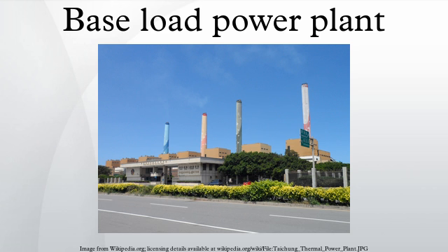Because they require a long period of time to heat up to operating temperature, these plants typically handle large amounts of baseload demand. Different plants and technologies may have differing capacities to increase or decrease output on demand. Nuclear plants are generally run at close to maximum output continuously, while coal-fired plants may be cycled over the course of a day to meet demand. Plants with multiple generating units may be used as a group to improve the fit with demand, by operating each unit as close to peak efficiency as possible.